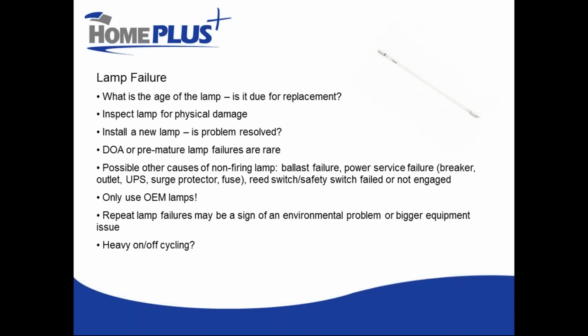So lamp failure is something that happens. It is a little bit less common than people think. One of the things that we see is people jumping to the conclusion that because I have a UV problem, my lamp output must be poor, and they jump in there right away and replace their lamp. And you know what? Sometimes that fixes the problem. Sometimes it fixes it because the problem was the lamp.